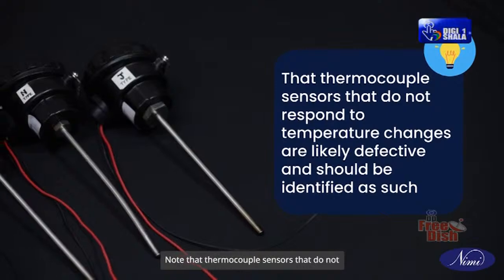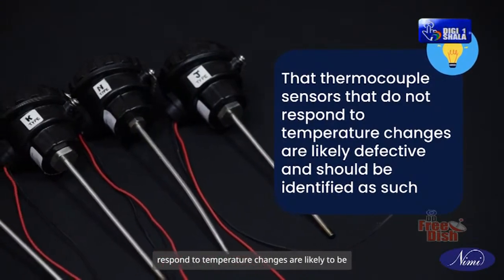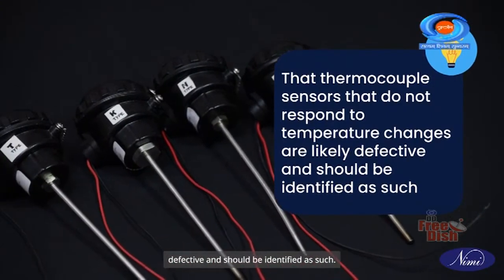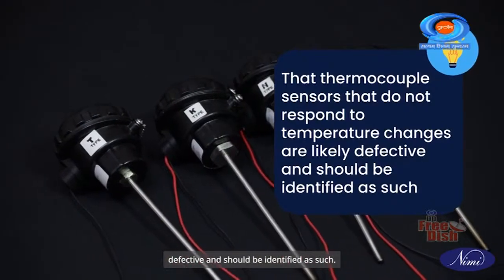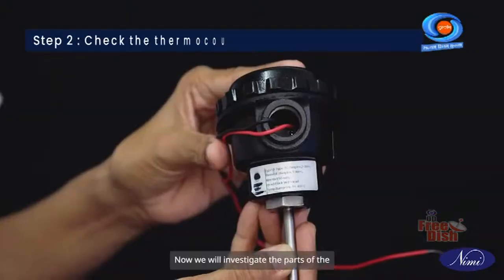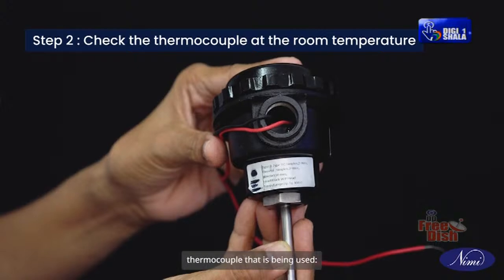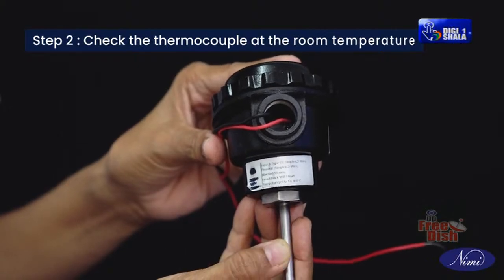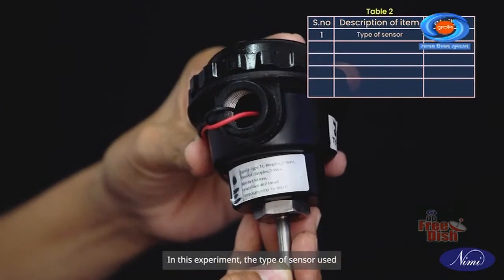Note that thermocouple sensors that do not respond to temperature changes are likely to be defective and should be identified as such. Now we will investigate the parts of the thermocouple that is being used. In this experiment, the type of sensor used for temperature measurement is type J.